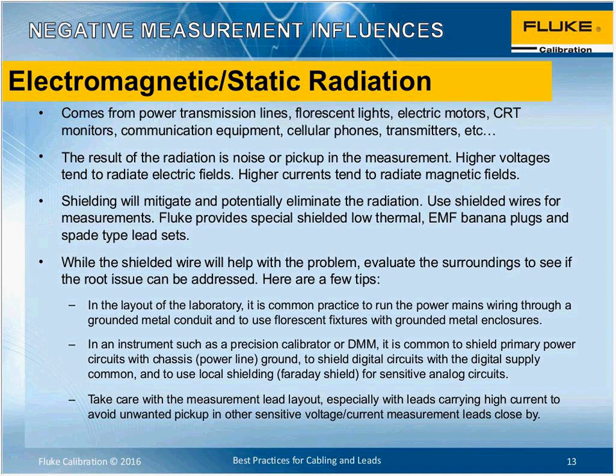And as already hinted, the design of an instrument such as a precision calibrator or DMM would probably have a well-shielded power supply within the instrument. But some of the more general purpose instruments, things like power supply units you might have on your bench for use during some tests, which may not be part of your precision calibration but happen to be there because you've used them in a previous test, might be a source of interference. So be careful.